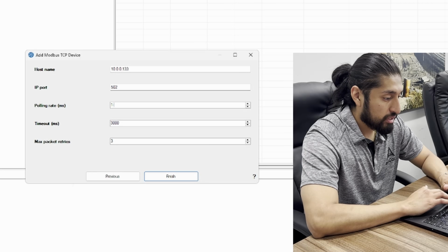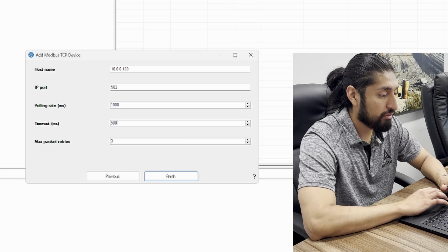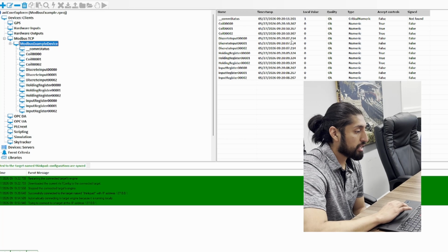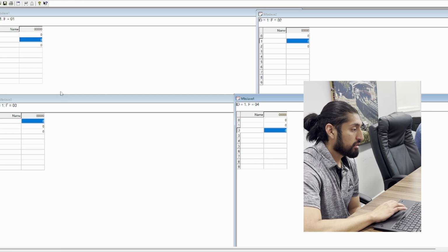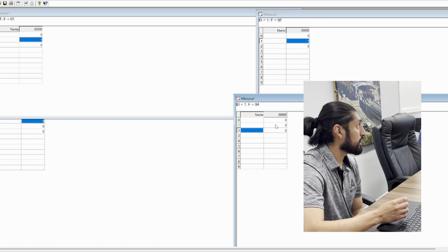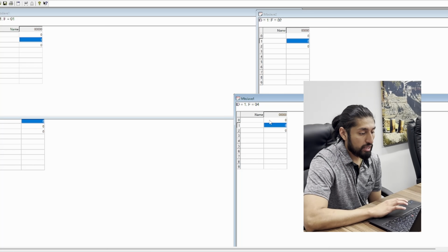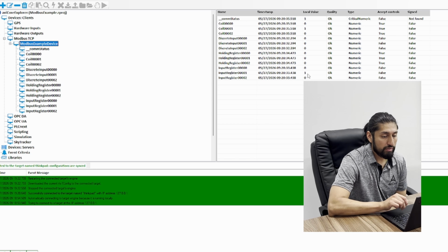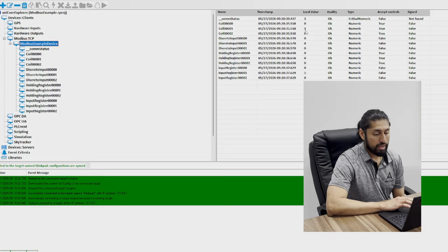Okay. We can also set the polling rate, how fast we want to poll this Modbus device, the timeout seconds again for Modbus, and how many retries we have if any communication failure happens. Okay. Next step is we can actually start reading the data coming from the device. Mm-hmm. So we just need to get this configuration over to the engine so that it can start reading the information. So in this case, the device itself, the aviCore engine, can be on the same device as this configuration application, or it can be a standalone device.